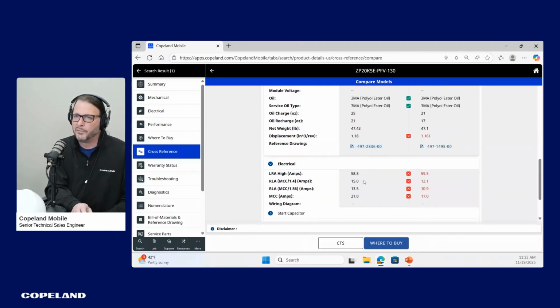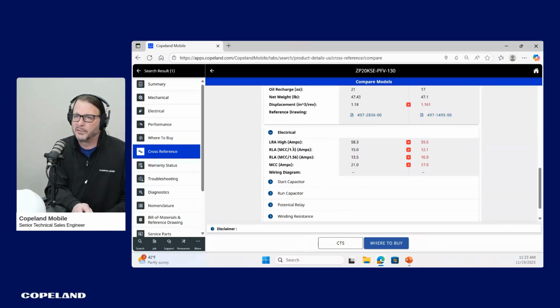Other important stuff for the service guys is electrical. It shows this RLA value, which Copeland uses to choose contactors and wire sizes and whatnot. I see that my RLA value is actually slightly lower, so I'm good with my contactor and my wires.